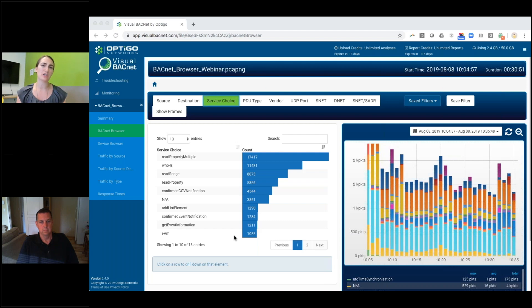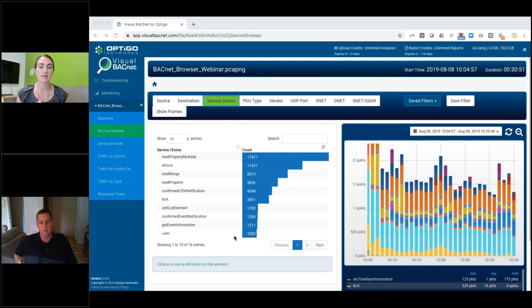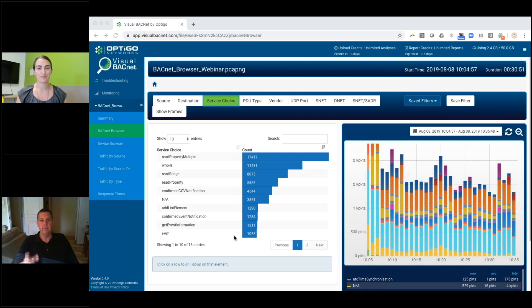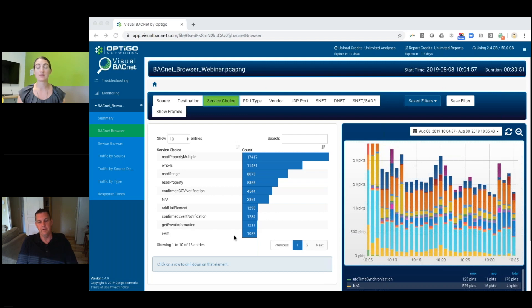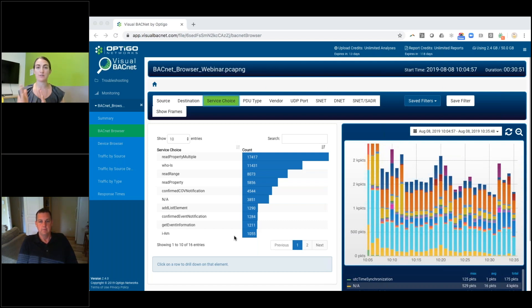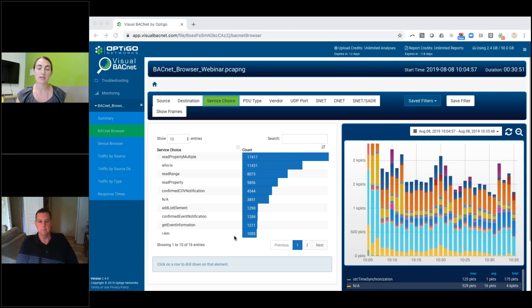But still not super normal. If you have a fairly static system, it shouldn't be doing a lot of looking for who is this device. So that might be something to look into. Don't always be too alarmed with that as well. Different BMS manufacturers, they will just do a check every so often to see if the device is online. And that could be part of what this is. So it's very manufacturer dependent. Yeah, absolutely. Good point, Ryan. And if that's the case with some manufacturers, you can change the frequency, but you can't stop it altogether. So you might be able to change it from one minute to half an hour, but it's still going to have to happen every half an hour. So there may or may not be some play in there.